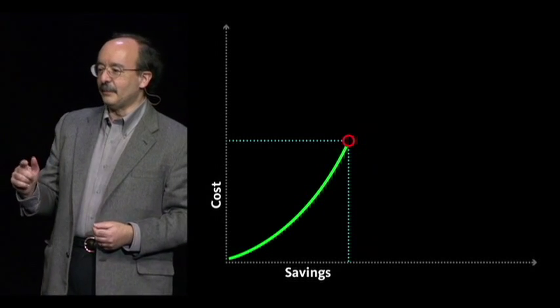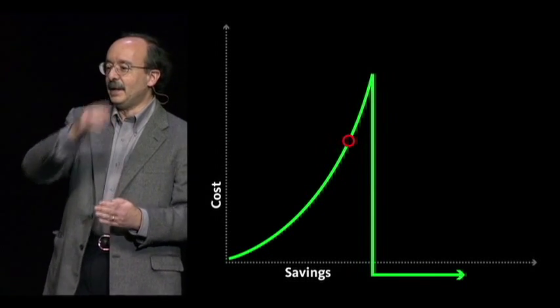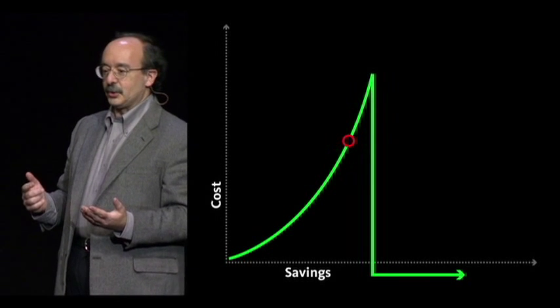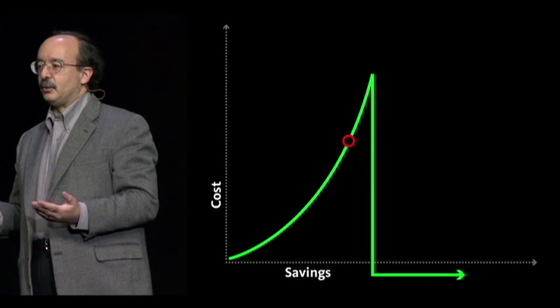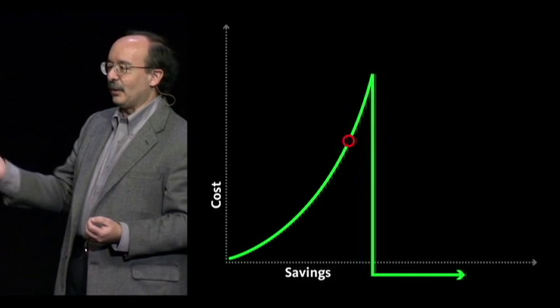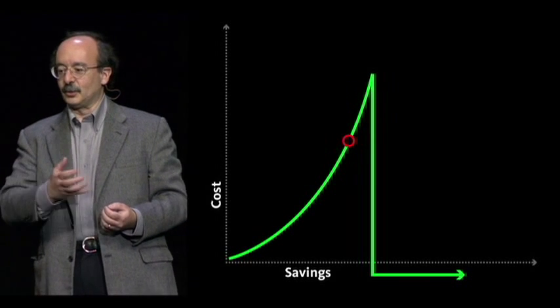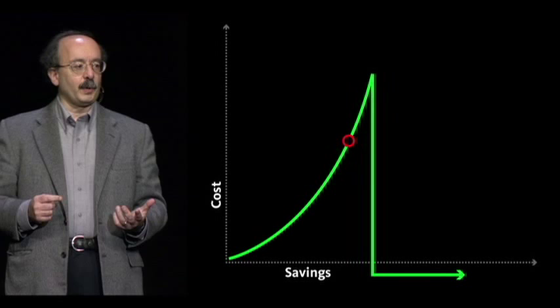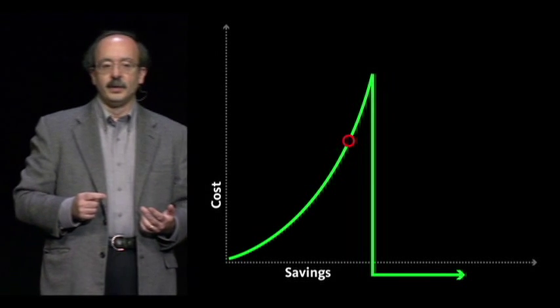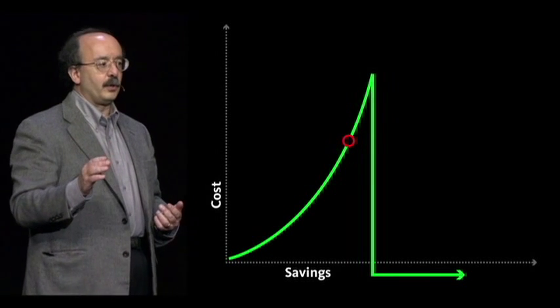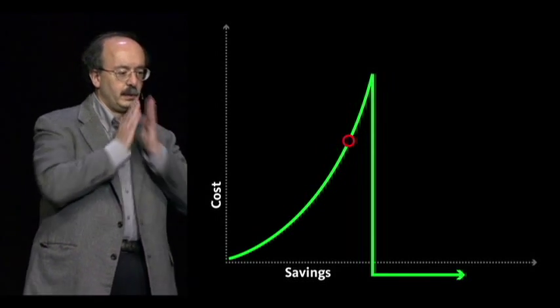But if you keep investing beyond that limit, you reach a point where suddenly your marginal cost goes down, for example, because you no longer need a furnace, ducts, fans, pipes, pumps, wires, controls, fuel supply arrangements. That's what I call tunneling through the cost barrier to achieve expanding returns to investments in efficiency.